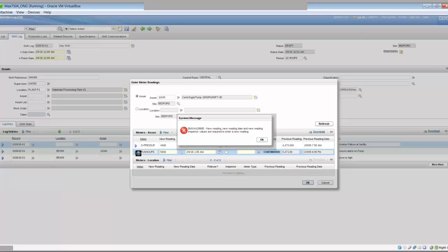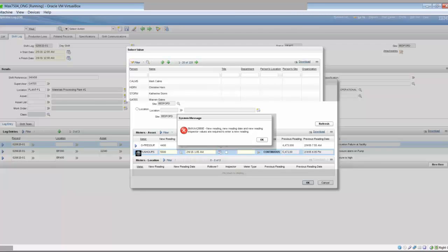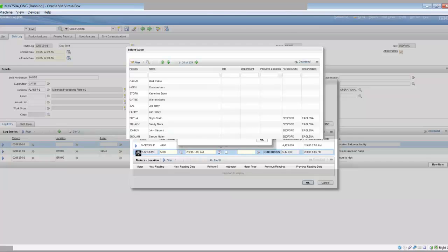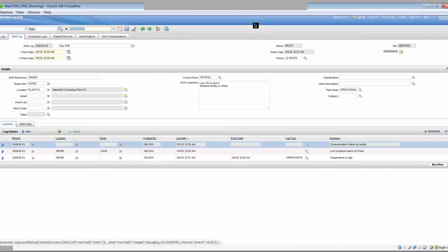So again, if you had maybe a condition monitoring point that said if the pressure goes below a certain point or above a certain point, and now maybe you're outside of your manufacturer operating pressures, or maximum operating pressures, it may create a work order automatically using the Maximo tool, or run hour is a perfect example if you just have some meter-based PMs that you want to kick off. Again, maybe some of the folks in the control room have better access to that.